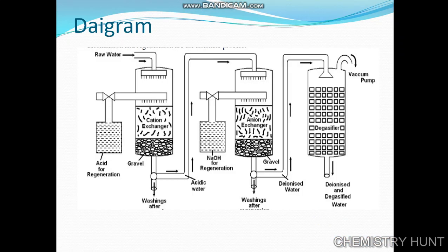Diagram: this is a raw water inlet going into the cation exchanger with gravels. The washings exit here. The acidic water is passed into the anion exchanger, also with gravels and washings. The deionized water which comes out is passed into the degasifier. The cation exchanger is regenerated by acidic solution, and the anion exchanger by alkaline solution.